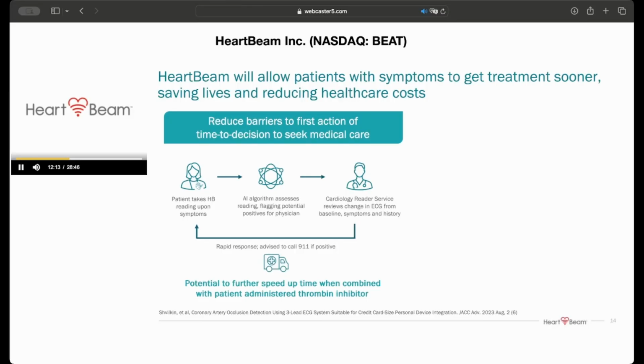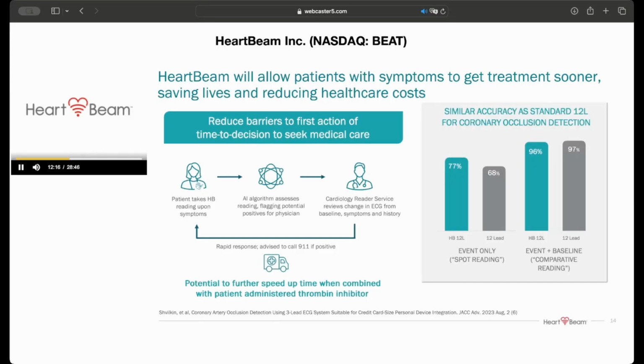On the right-hand side, you'll see as it builds here that we've done proof of concept studies. These show that the accuracy of a 12-lead standard ECG and our system are similar. But also what's interesting is the accuracy of either of them, as you see on the far right, increases significantly when the ECG is compared to the patient's own baseline, as it's the change in signal and the presence of symptoms that's really crucial. So what the chart really shows is that our system by design always has a baseline, and that can significantly outperform a 12-lead taken in the emergency room, comparing those two middle boxes there. If the patient in the emergency room is not a known patient, there's no reference ECG. So that's where we potentially could actually exceed the current standard of care.